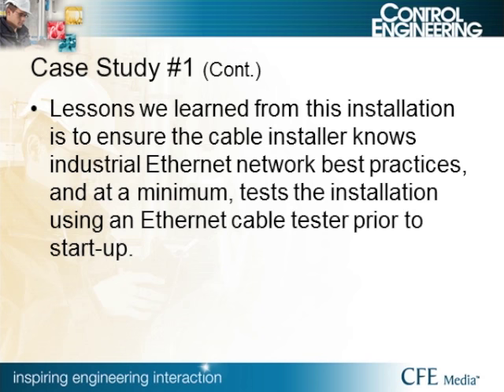Lessons learned from this installation: ensure that whoever's installing knows industrial Ethernet network best practices — there's a lot of information out there from various societies and distributors. At a minimum, make sure you're testing every connection. Get at least an Ethernet cable tester, and if the project can afford it, a cable qualifier or certifier. Cable qualifiers and certifiers keep a record of each cable tested, including length, crosstalk across pairs, what the cable can be rated for, and speed. This data can be printed out and attached as part of the startup record set.